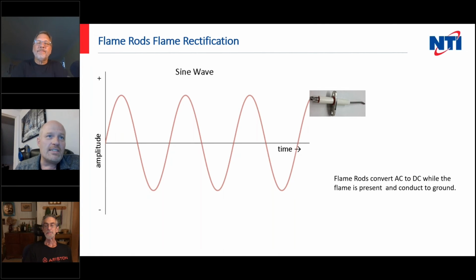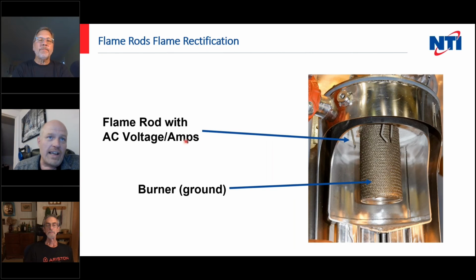What our flame rod does to this AC current is it rectifies it. Rectification means it takes an AC voltage and turns it into a DC voltage. What the DC voltage means is that instead of going up and down, it turns into a straight line. So it becomes +5 volts or +10 volts or whatever it becomes. It's a single voltage signal. The way this occurs is we apply AC voltage to our flame rod. So there's our flame rod. It sits in the flame that comes from the burner, and the burner is actually just an electrical ground.